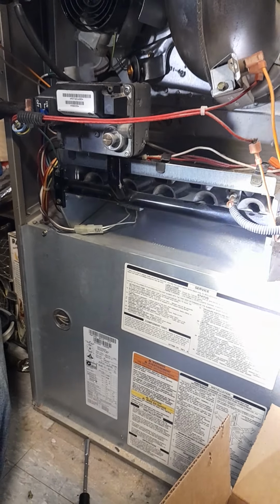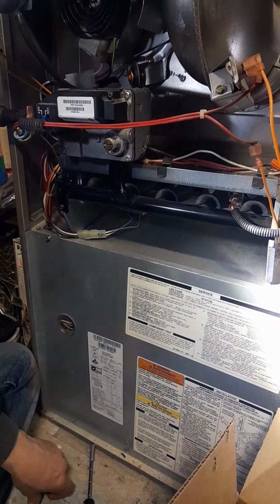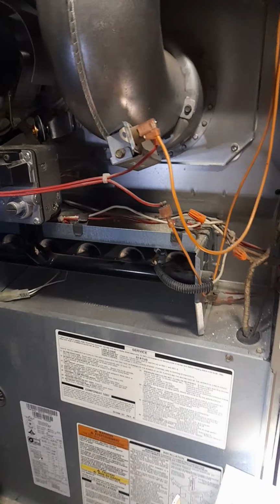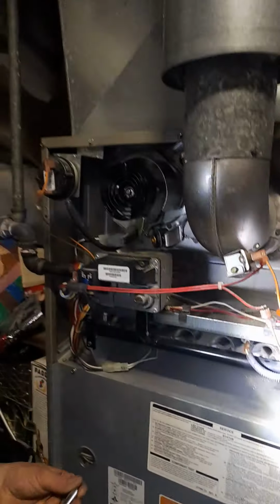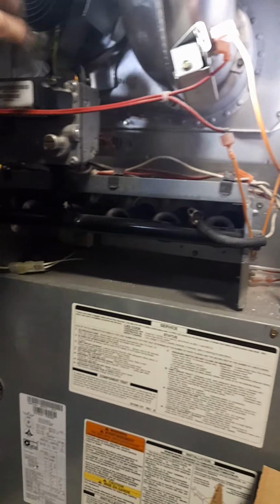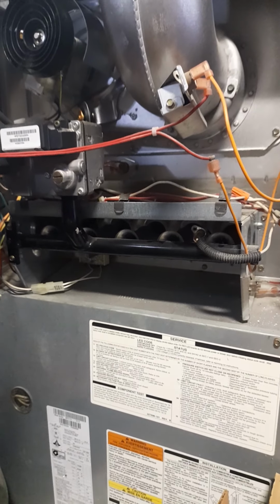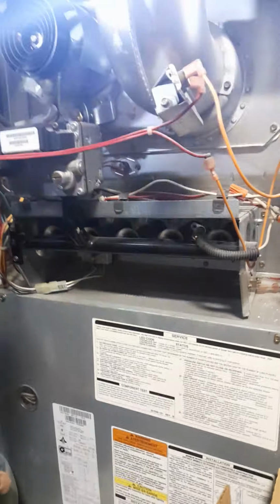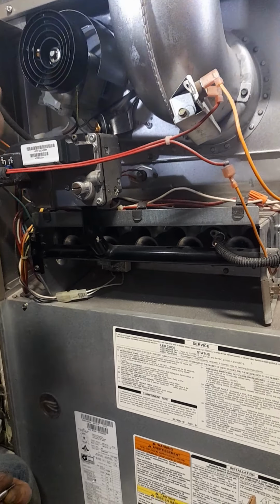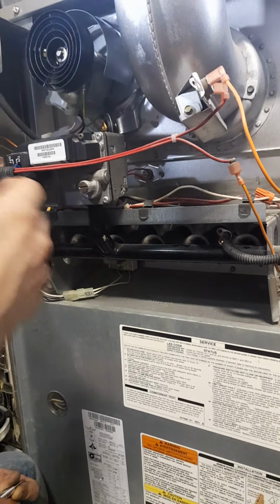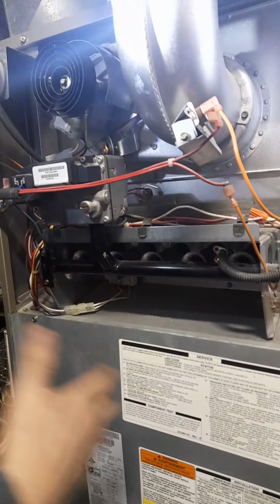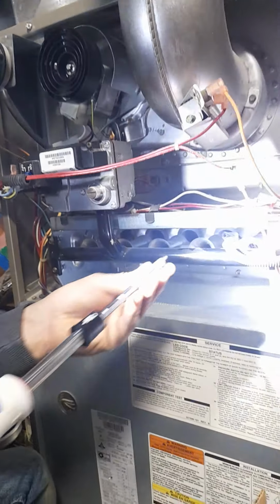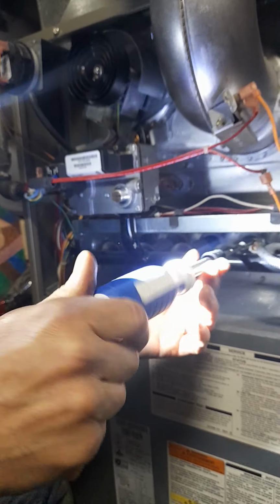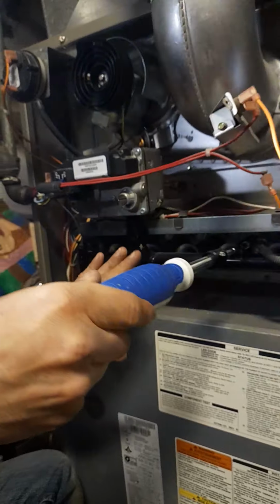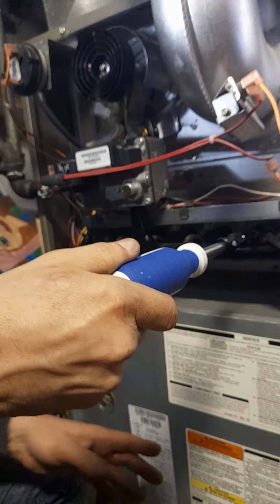However, some furnaces never actually give you an error code if the pressure switch should fail because this bearing should, let's say, seize the fan from spinning, and then let's say the vacuum drops below 0.27 inches. So there you should actually get an error code. But some furnaces don't give you an error code because it's already committed to a burn cycle, and the flames will disappear because it dropped, but it won't give you an error code.